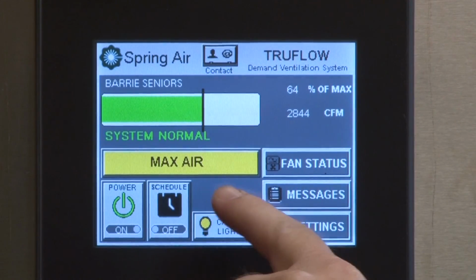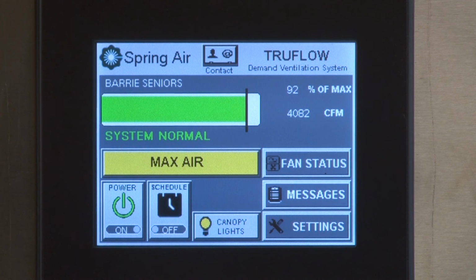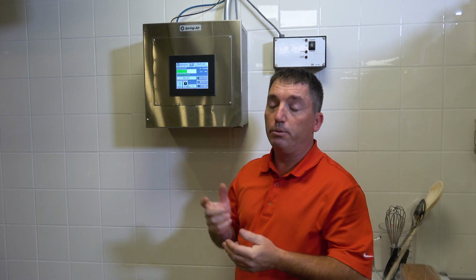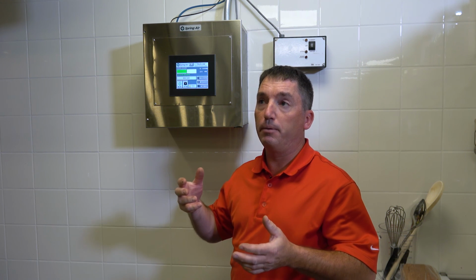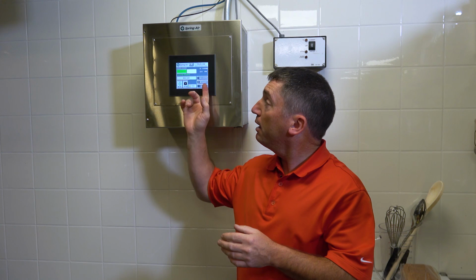The one exception to that is if you put a handful of steaks or something that produces a lot of smoke on the grill, there is a manual override button here that says max air. If you press that button once, it will turn yellow and you can hear the exhaust system ramp up to full speed. To go back to normal operation, you can just press that again to cancel it. The green bar basically is going to show you what level of total capacity you're running at, and that will adjust automatically based on the cooking load.